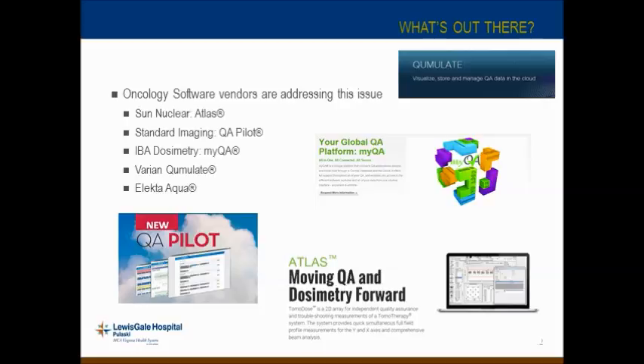Most of these have very nice web interfaces where you can see your QA in real time, viewable from other facilities. As an HCA facility, we have somewhere north of 80 cancer centers, and a larger corporation may want to use something like Varian Qumulate to aggregate QA from many centers regardless of which other software platform is being used. The big question going forward is how interchangeable the data is between these systems — is there a standard format? If you have a Standard Imaging beam checker and want to import data into Atlas or MyQA, will it be readily accessible? Cross-platform data transfer is something to evaluate before committing to an electronic QA setup.